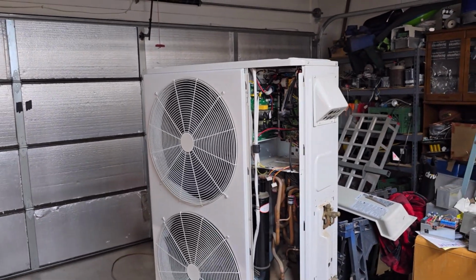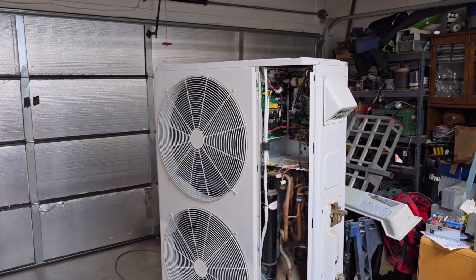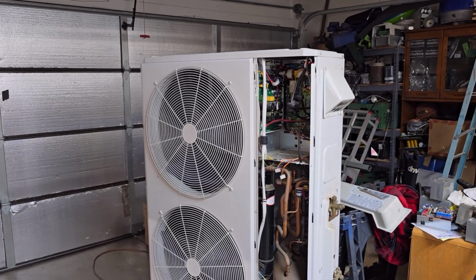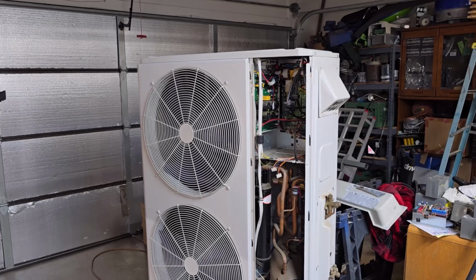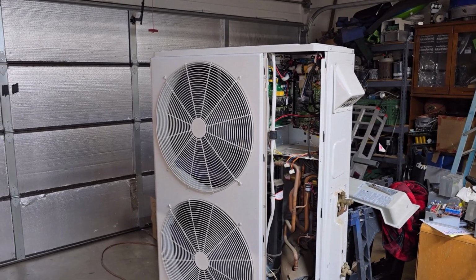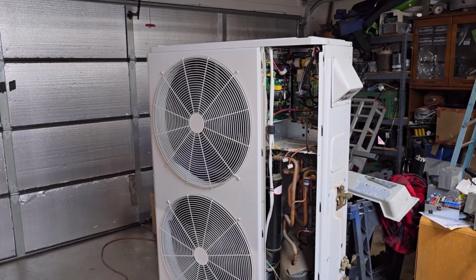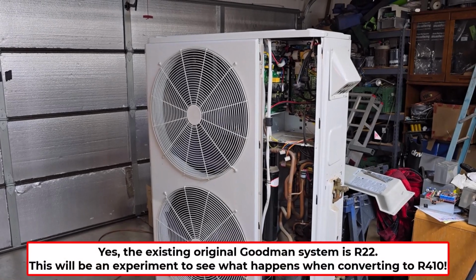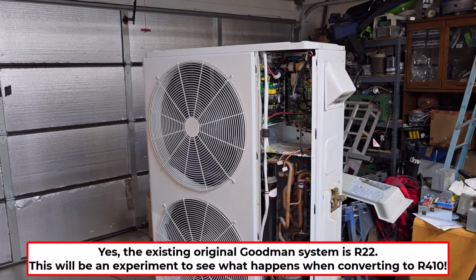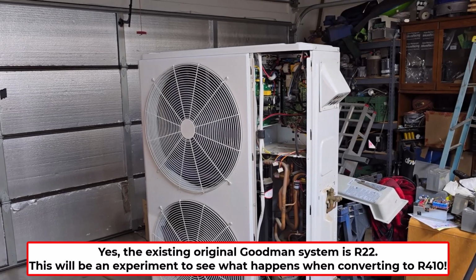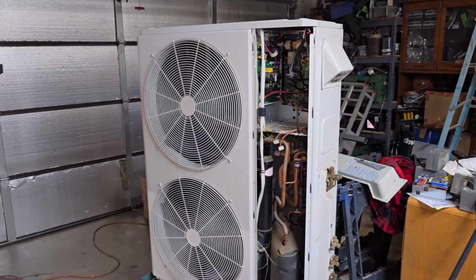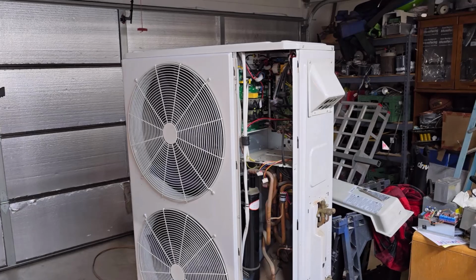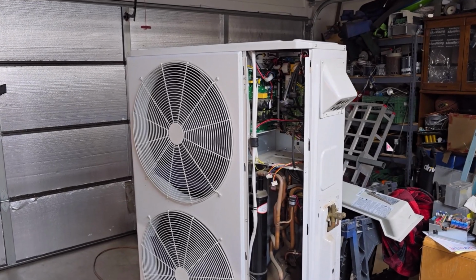I think I'm going to just put an ECM blower in that Goodman up there, change the cartridge and the power head on the Sporlan TXV I put in there when I first moved in - it's an R22 one right now, I'm just going to change it over to R410. And I think I'll just hook a 410 outdoor unit to the old Goodman and say screw it, see what happens.